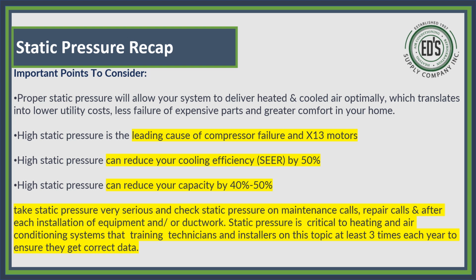But it will. So you look at that, the unit ran nonstop because it's 440 CFMs in a house that needs 800. So it's going to run. What that's going to do is run a higher light bill. All right. But also you're putting a lot of pressure on the compressor and a lot of pressure on that X13 motor. Here's why I say this.